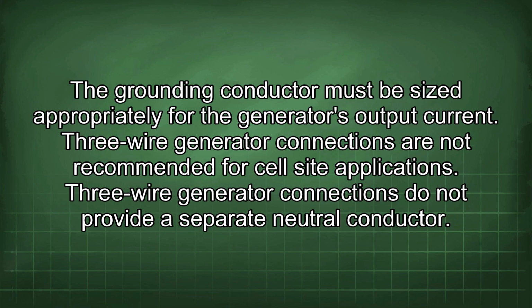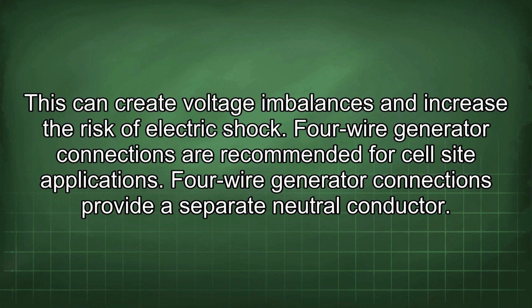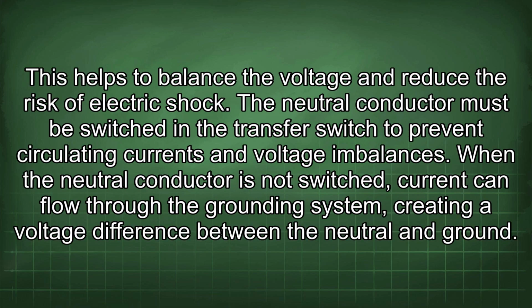3-wire generator connections are not recommended for cell site applications. 3-wire generator connections do not provide a separate neutral conductor. This can create voltage imbalances and increase the risk of electric shock. 4-wire generator connections are recommended for cell site applications. 4-wire generator connections provide a separate neutral conductor. This helps to balance the voltage and reduce the risk of electric shock.